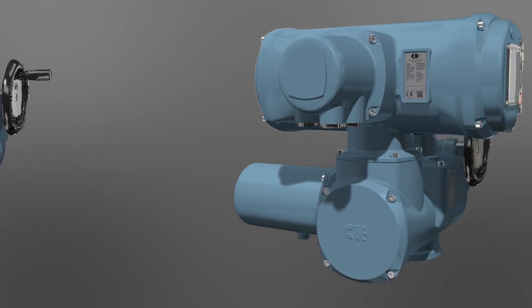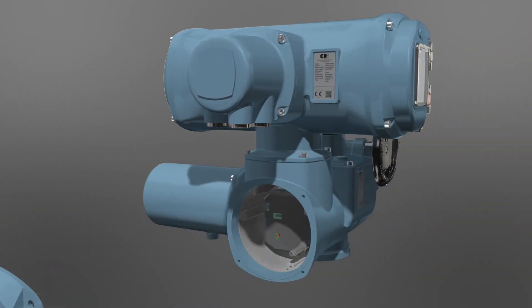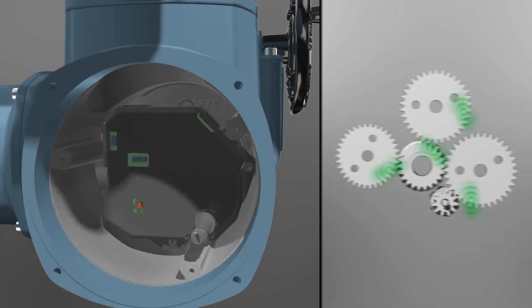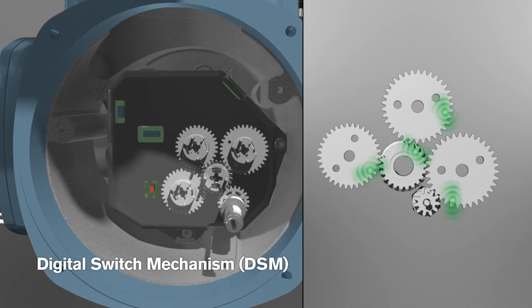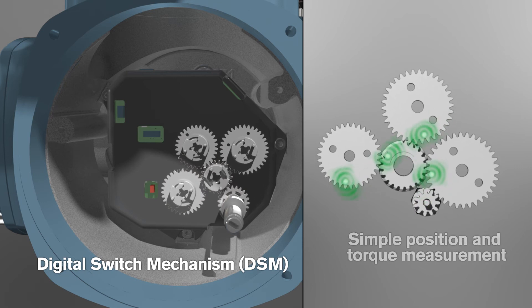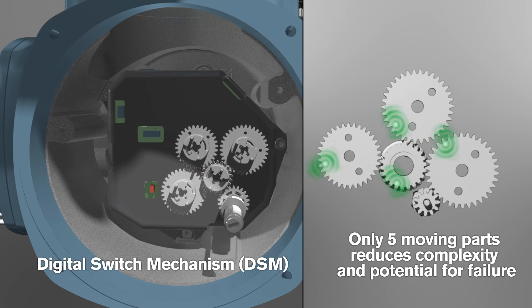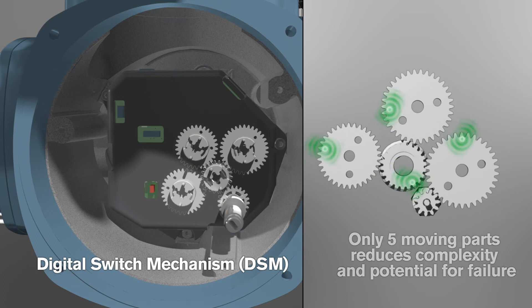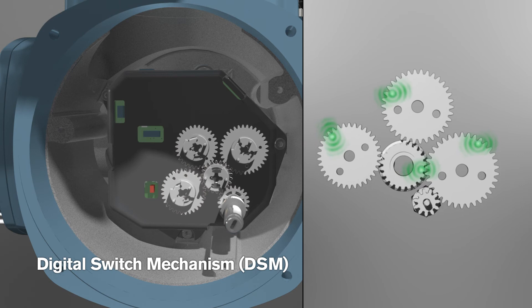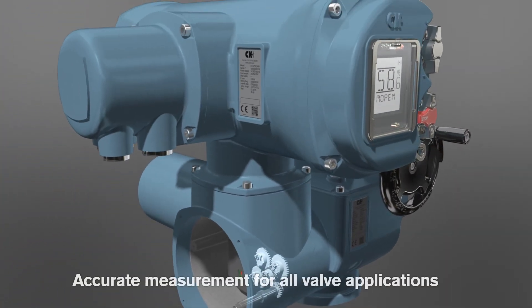The CK digital switch mechanism is designed for exclusive use with the CK Centronik control module. Position and torque are measured using a contactless absolute encoder arrangement consisting of only 5 moving parts. Total valve travel up to 8,000 turns can be accommodated with this encoder system, whilst torque can be adjusted from 40% up to 100% of rated torque.